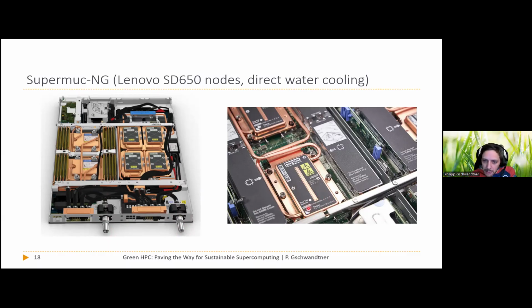At the bottom, barely readable across the live stream, is the torque: 1.4 to 1.6 Newton meters, the amount of torque allowed or needed to tighten the screws. If you tighten them too little, there might be water leakage or not enough cooling contact. If you tighten them too much, you might break the hardware, or again create physical tension that worsens the cooling contact.